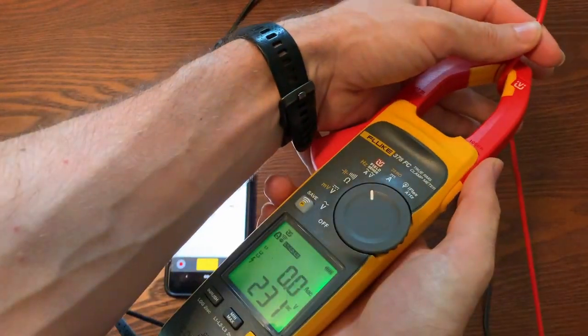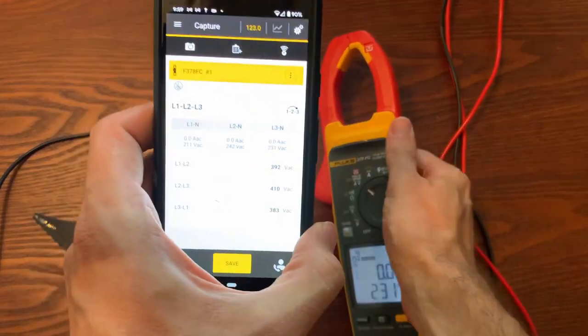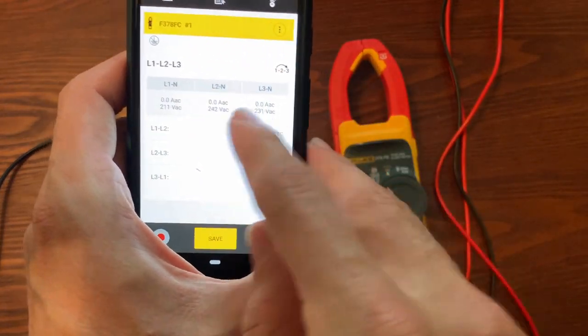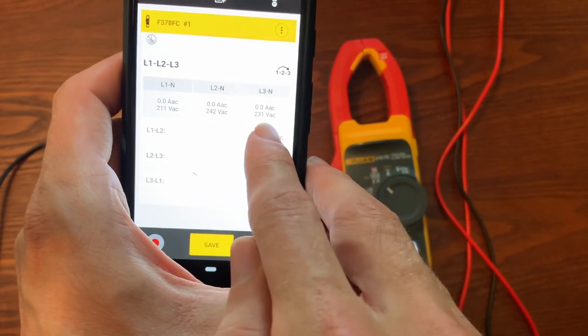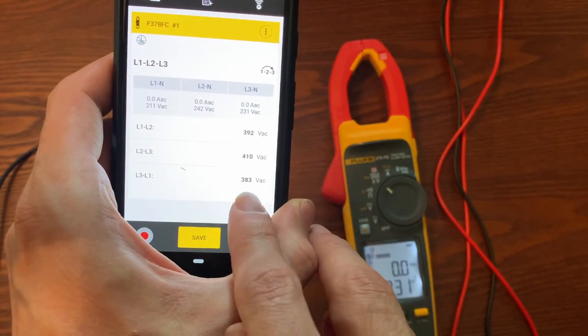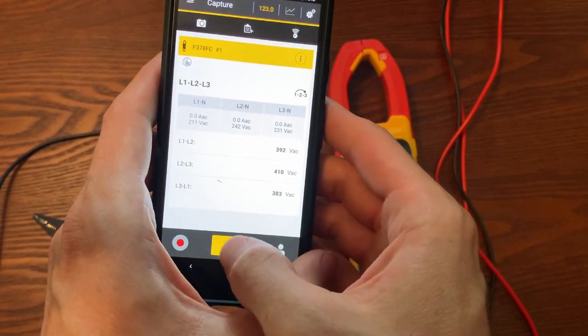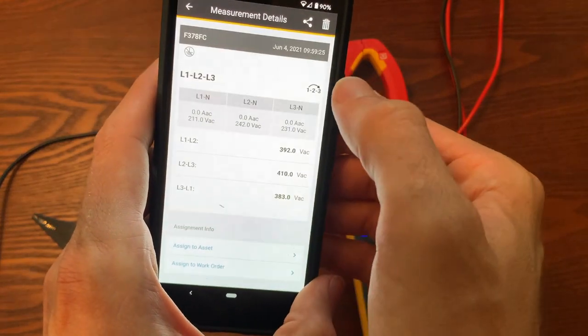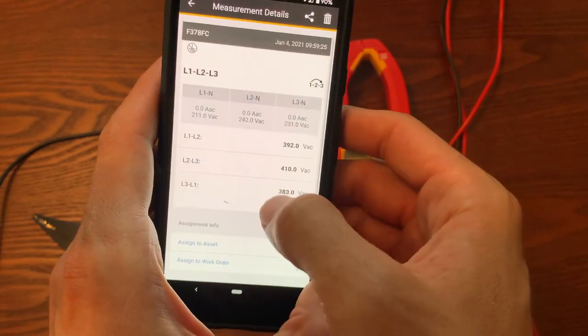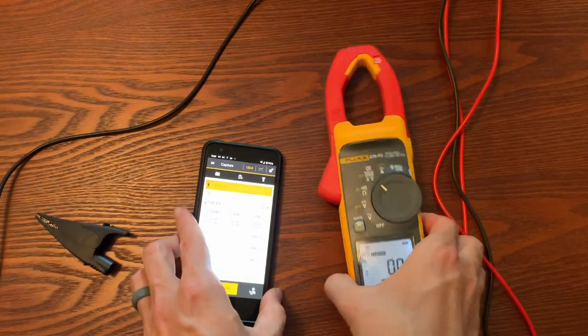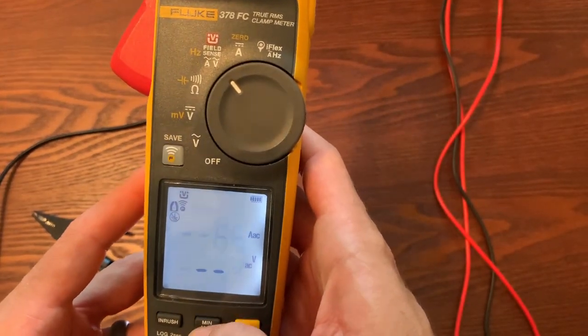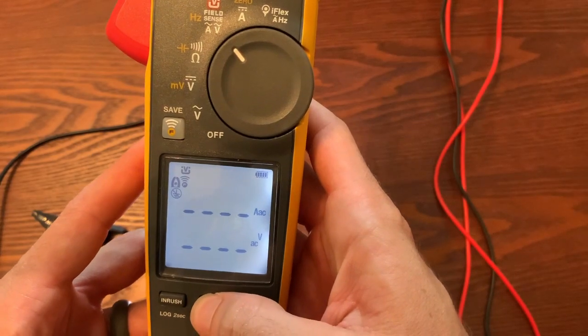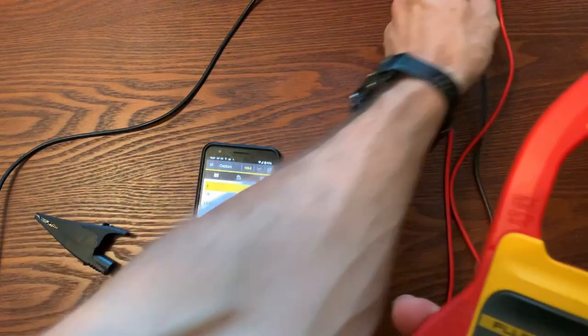The advantage of doing this connected to the phone is you're going to see all of your readings. You're going to see leg one, leg two, leg three voltage to neutral potential as well as leg to leg. And it's going to give us phase rotation which you see in that arrow that arcs over in the clockwise direction, says one two three. I'll do this a second time and I will change the order in which I measure the three phases and you will see the arc of the phase rotation will then point counterclockwise showing you the phase rotation. So this is a way that you can measure phase rotation without making physical connections to energized circuits.